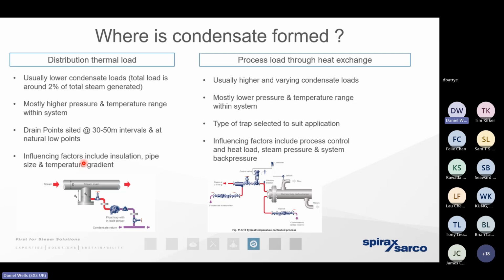And that 2%, that 200 kilograms, can then help us to determine the size or the capacity of the steam trap and where we need to locate them. And it will also help us to size the condensate return infrastructure as well. Now that's what we call the running load. And the running load assumes that the infrastructure's nice and hot 24/7, 365. In reality, the boiler is going to be switched off for certain periods of the day, or the steam infrastructure to different buildings is going to be isolated for different reasons. So we need to take into account what we call the warming up load. And the warming up load assumes that in the first few moments, more and more of the steam is going to condense in the pipework as it gives up its energy to the infrastructure. It's only for a relatively short period of time, maybe an hour or so, but it's vitally important that we take that increased condensing load into account as the infrastructure is warming up.